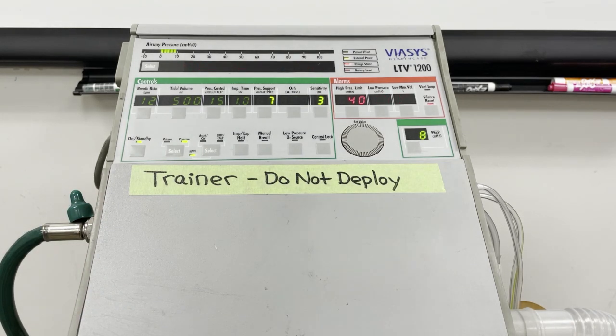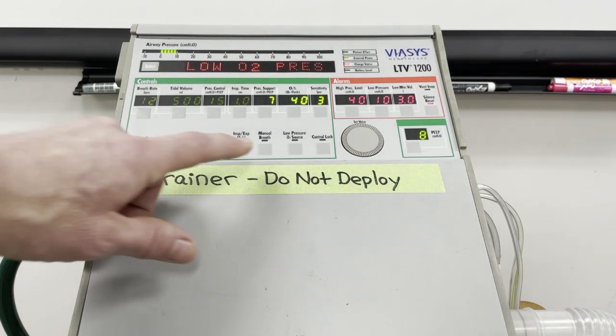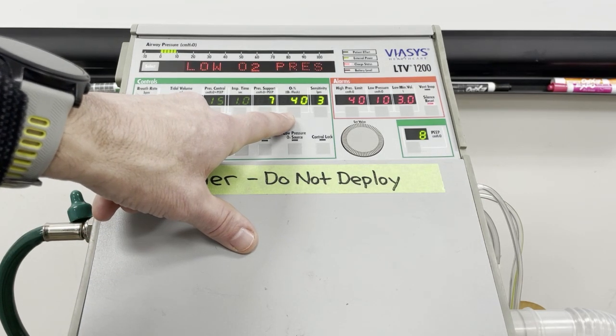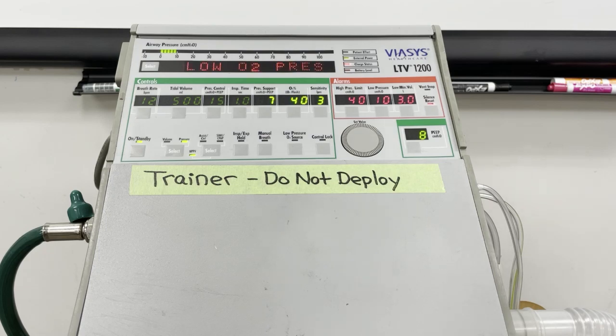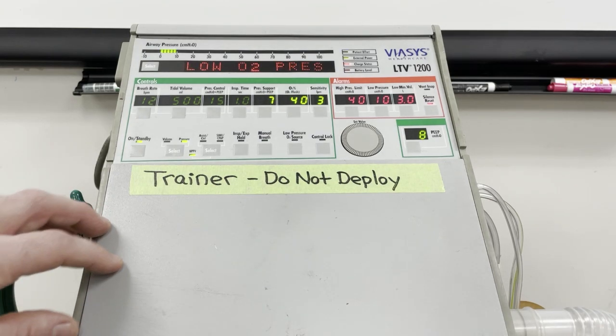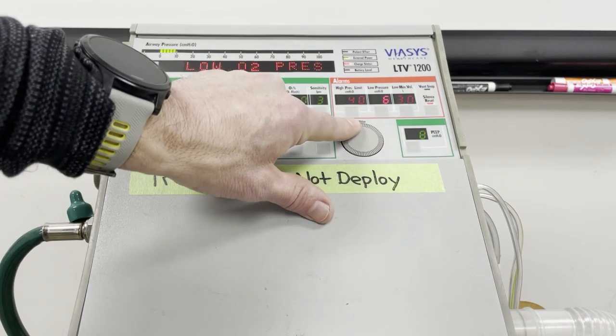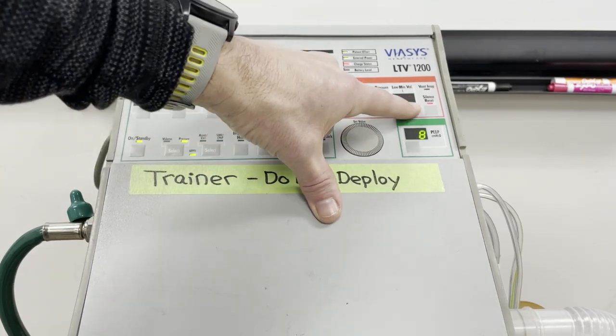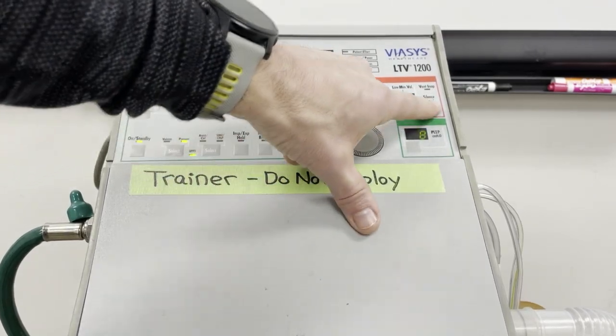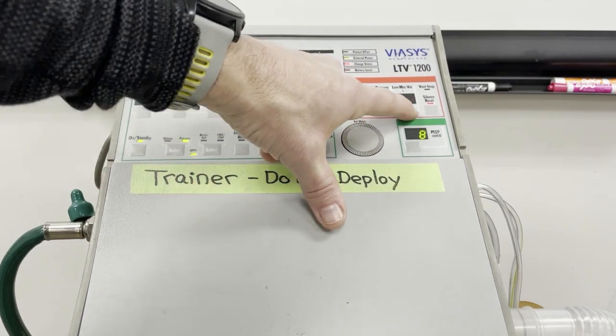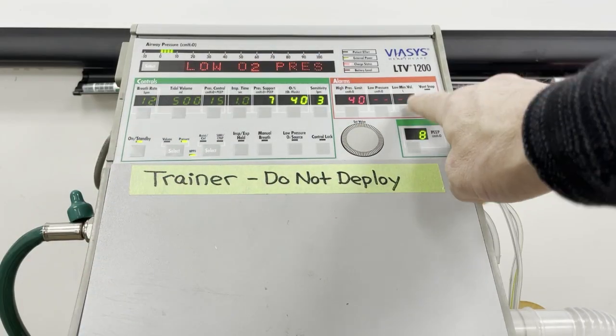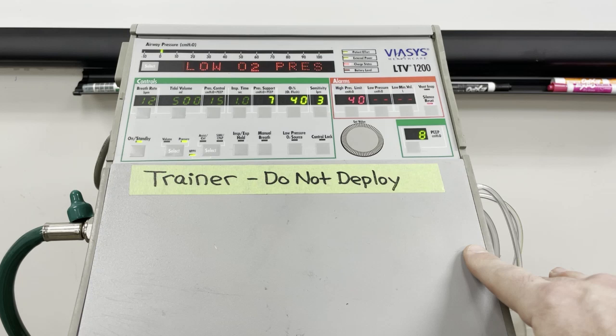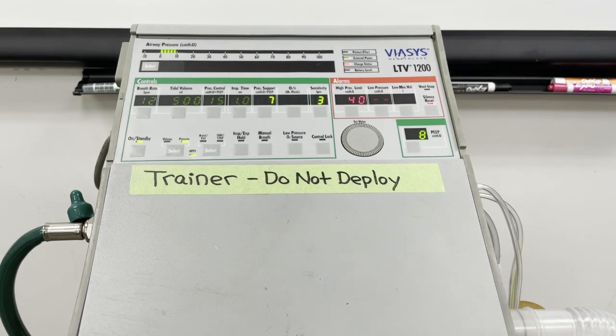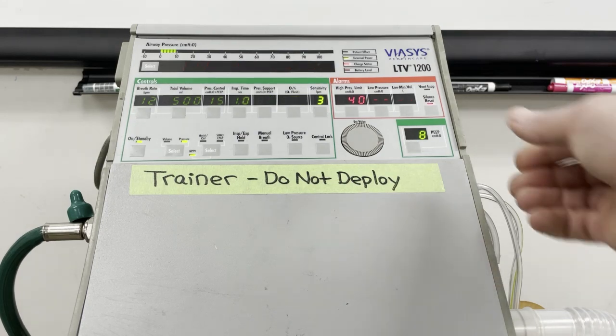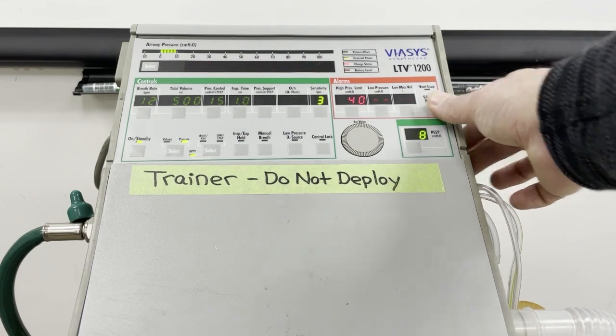You're not done yet. Make sure that the oxygen concentration is set to the prescribed amount. Next, dial down the low pressure and the minute volume until it says dash dash. These limits are not necessary because the patient is conscious and breathing on their own. If you don't get rid of them, they may trigger and become a constant headache during the call.